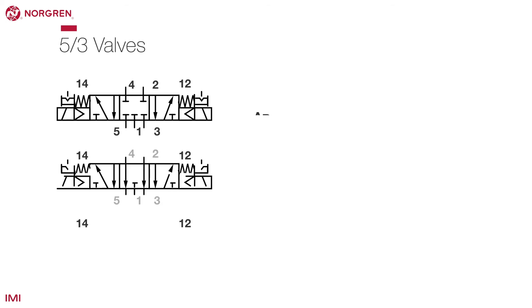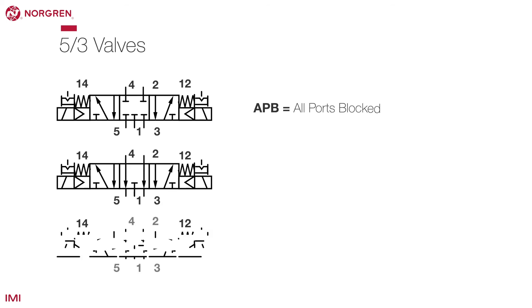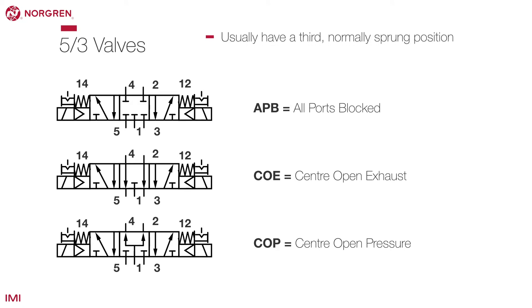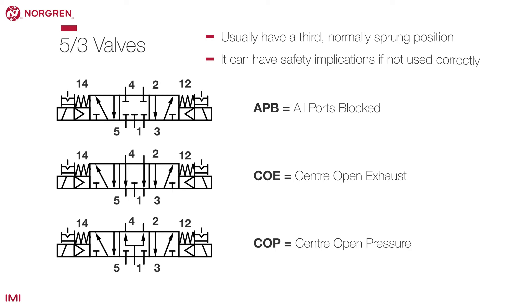5-3 valves are also available, but should only be provided in certain circumstances. These valves have a third normally sprung position and it can have safety implications if not used correctly. Ensure that the customer is replacing like for like — if not, then seek technical advice.